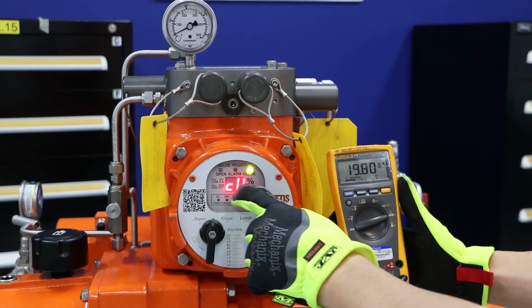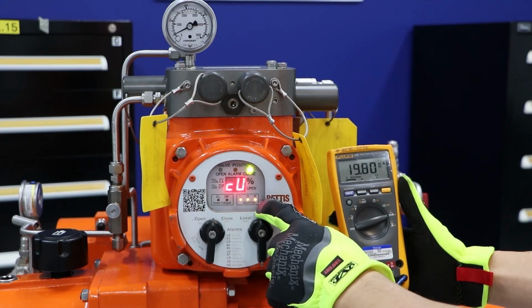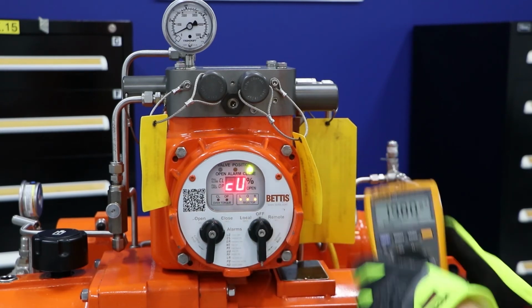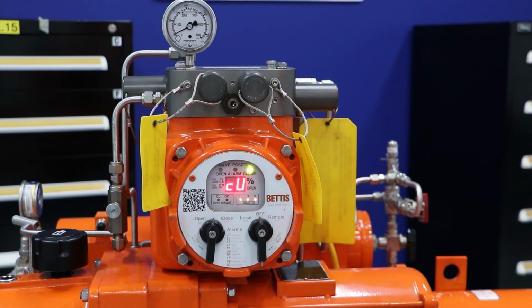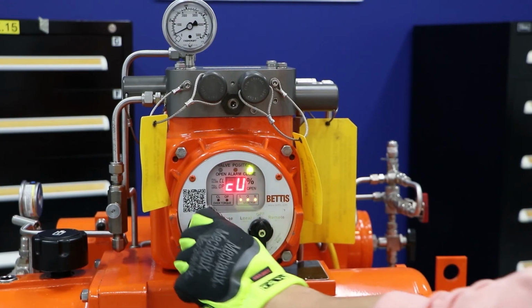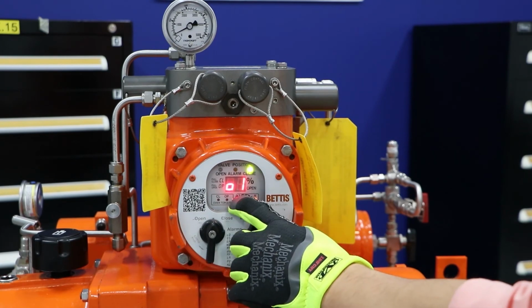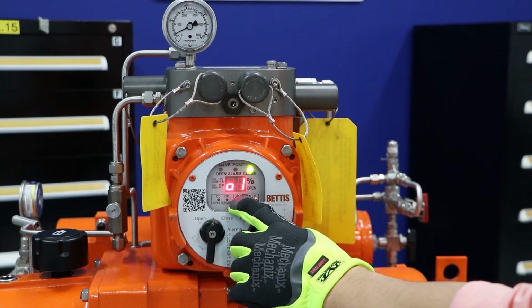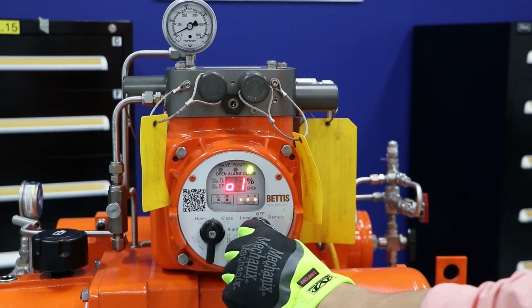All right. If it says CU, that means we've successfully set our upper limit for our analog output. If it says CF, that means it failed and we need to do this again. So in this case, we'll hit yes. Okay. When it reads O1, that means we've successfully completed our analog calibration for analog signal 1. Next, we want to save this configuration that we just did.